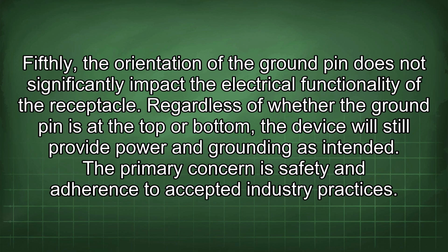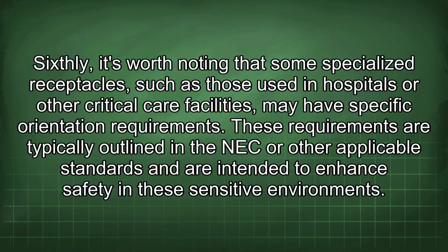Fifthly, the orientation of the ground pin does not significantly impact the electrical functionality of the receptacle. Regardless of whether the ground pin is at the top or bottom, the device will still provide power and grounding as intended. The primary concern is safety and adherence to accepted industry practices. Sixthly, it's worth noting that some specialized receptacles, such as those used in hospitals or other critical care facilities, may have specific orientation requirements. These requirements are typically outlined in the NEC or other applicable standards and are intended to enhance safety in these sensitive environments.